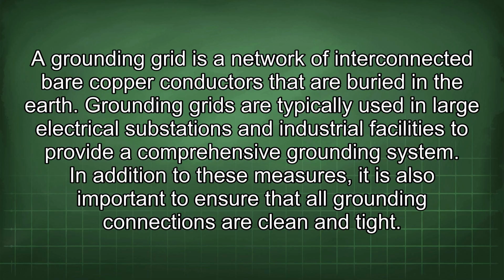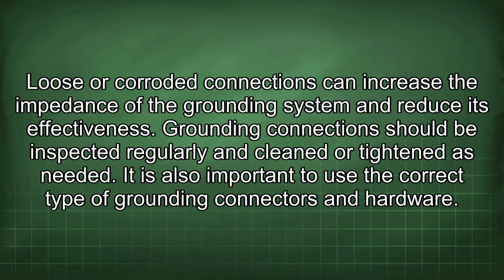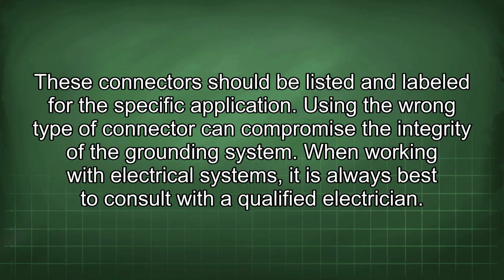In addition to these measures, it is also important to ensure that all grounding connections are clean and tight. Loose or corroded connections can increase the impedance of the grounding system and reduce its effectiveness. Grounding connections should be inspected regularly and cleaned or tightened as needed. It is also important to use the correct type of grounding connectors and hardware. These connectors should be listed and labeled for the specific application. Using the wrong type of connector can compromise the integrity of the grounding system.